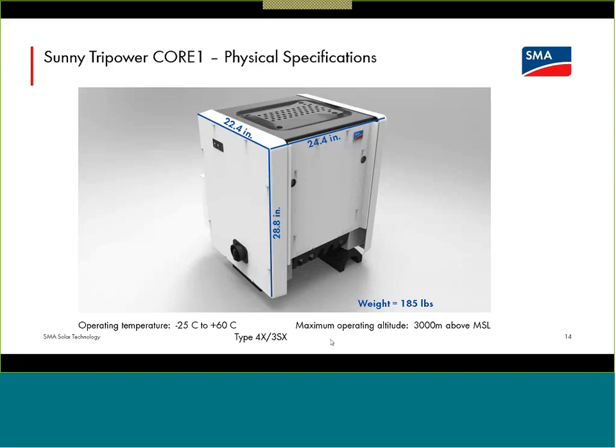Excellent. There are a couple questions coming in the chat window talking about this being able to be outdoors. Most definitely. Again, I mentioned the storage temperature down to -40°C. The ratings here, the 3SX rating is the testing for the AC and the DC handles to ensure they are operable if laden with ice or snow. And again, you're correct, definitely the airflow path is up the center of the device. This begins as a natural convection, just free airflow, and the fans that are in the fan tray are located here at the bottom center of that thermal chimney. They are speed controlled. So as the inverter temperature goes up, at some point the temperature sensor will turn the fans on, and then they're speed controlled based on the temperature of the inverter. If, say, a bird built a huge nest on the top of this device, that just means that the cooling of the device will be less efficient.